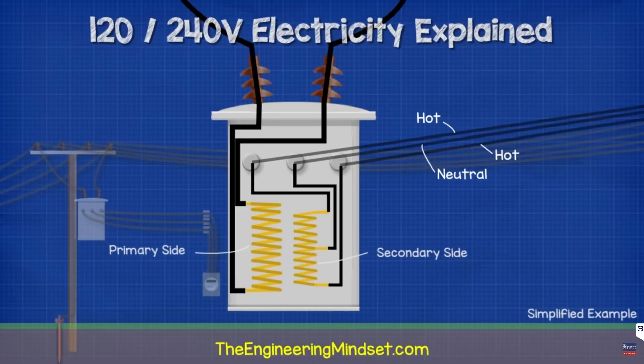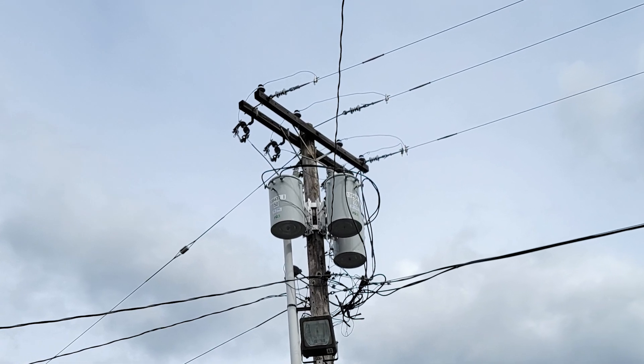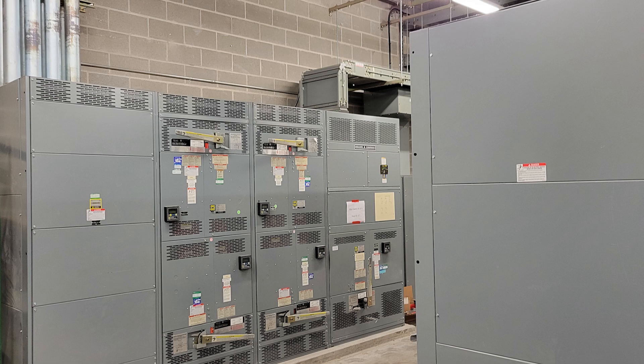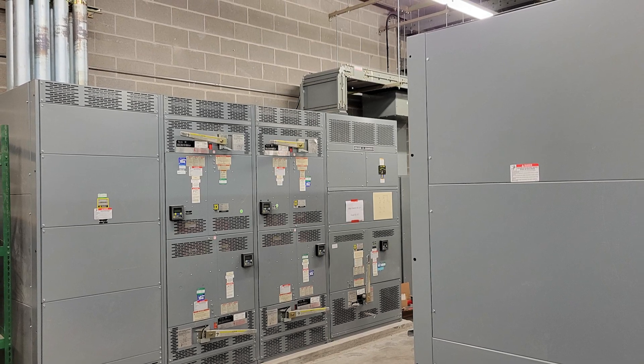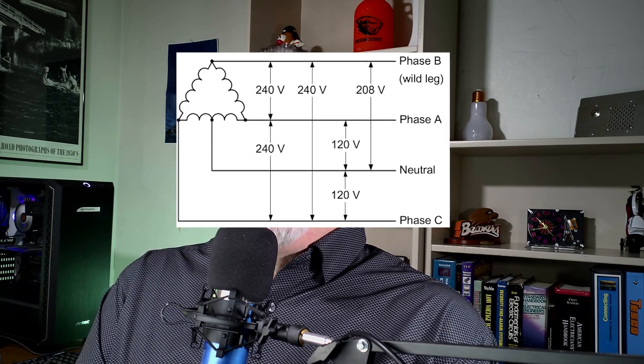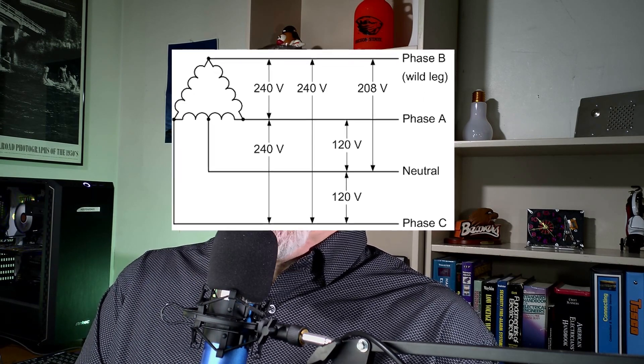We design all kinds of alternating current systems with different characteristics — everything from a 120/240-volt split-phase system in an American house, to a 208Y/120-volt three-phase four-wire system in a commercial building, a 480Y/277-volt three-phase four-wire system in a large commercial or industrial building, and even older systems like a 120/240 three-phase four-wire delta with split-phase, or a 480-volt three-phase three-wire corner-grounded delta.